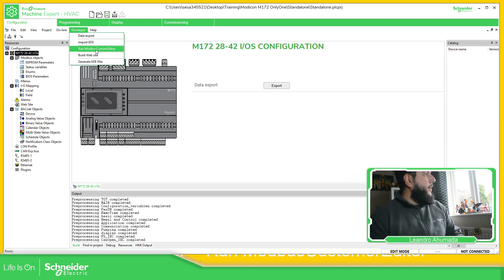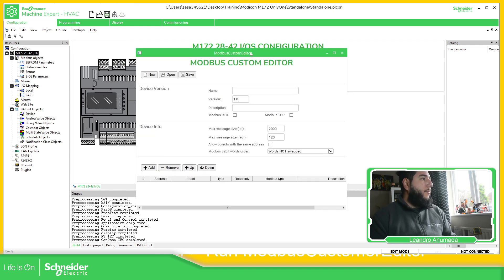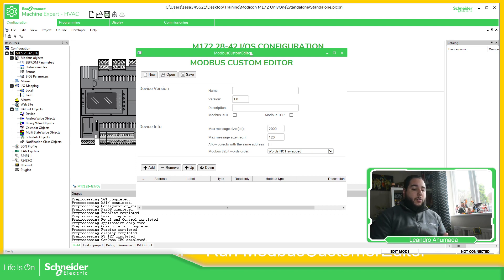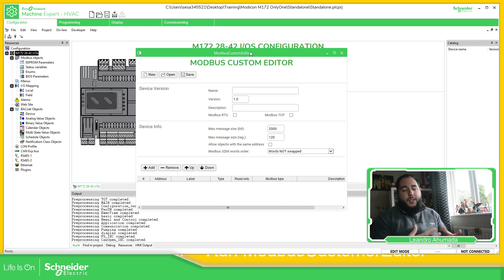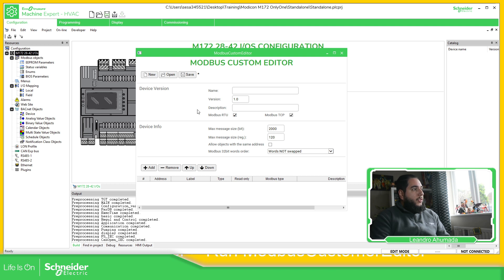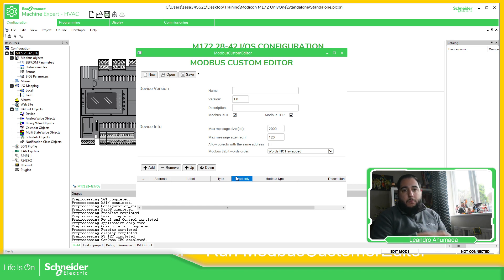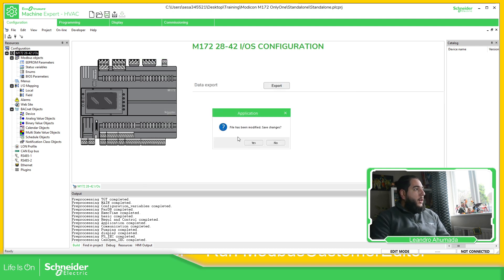There is also a Modbus custom editor. Basically, if you're using a different kind of application, you have the possibility to import EDS files, which contain information about the device you want to communicate with, to easily integrate it into your system. Here you can create a template for those EDS files, define a device over Modbus RTU and Modbus TCP, and easily add all the addresses. I'll cover that later, but I just wanted to show you what we have here.